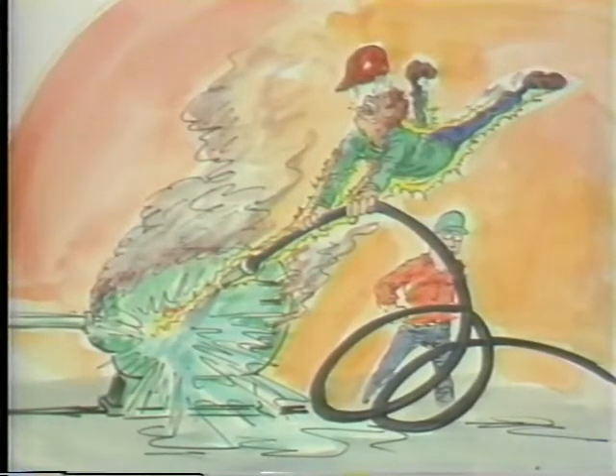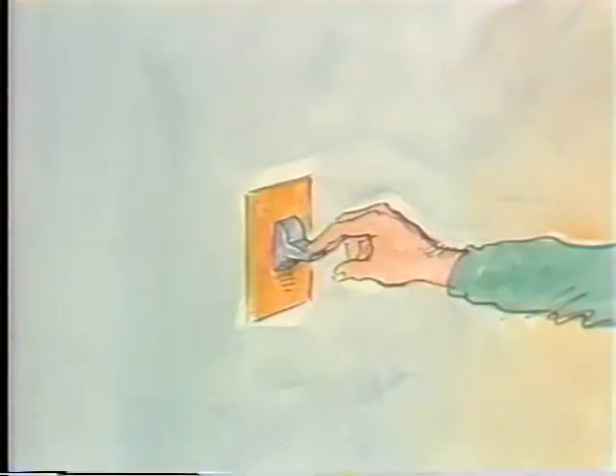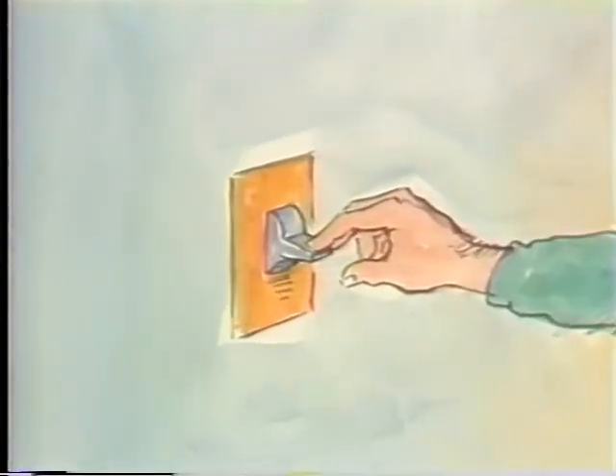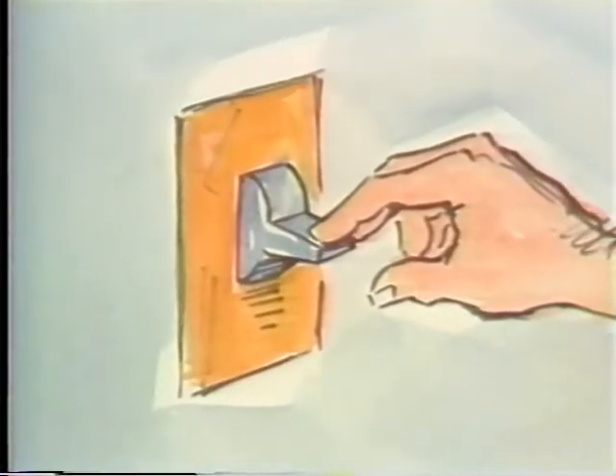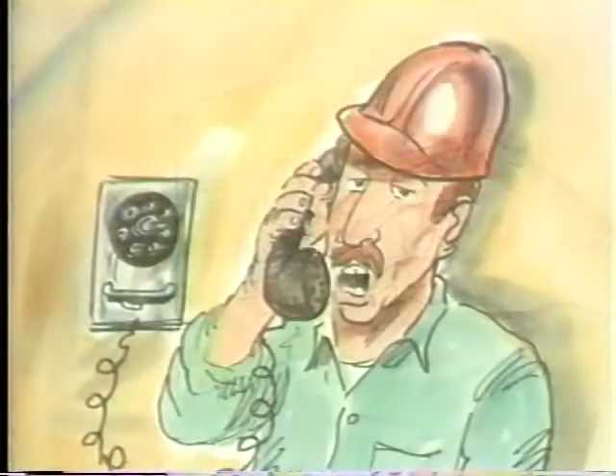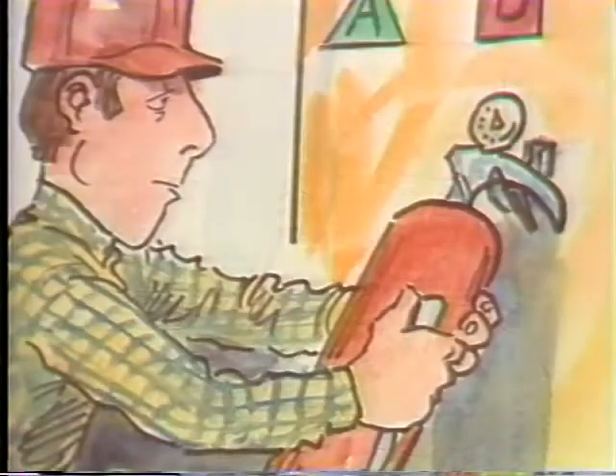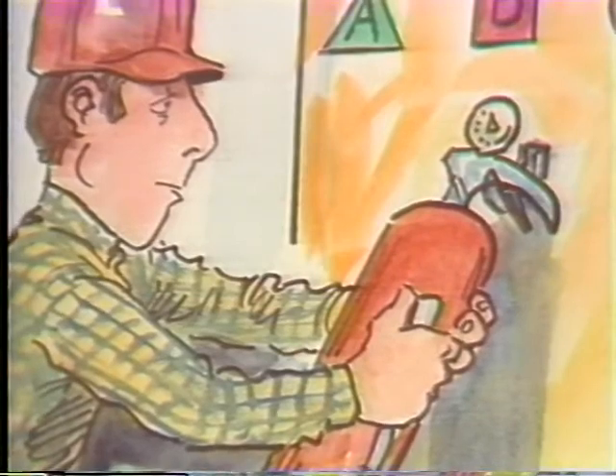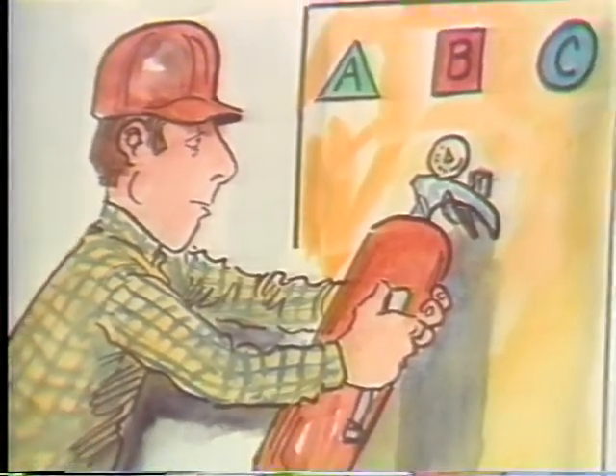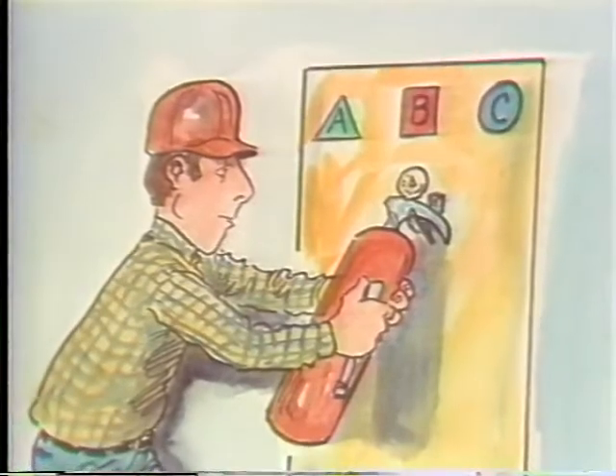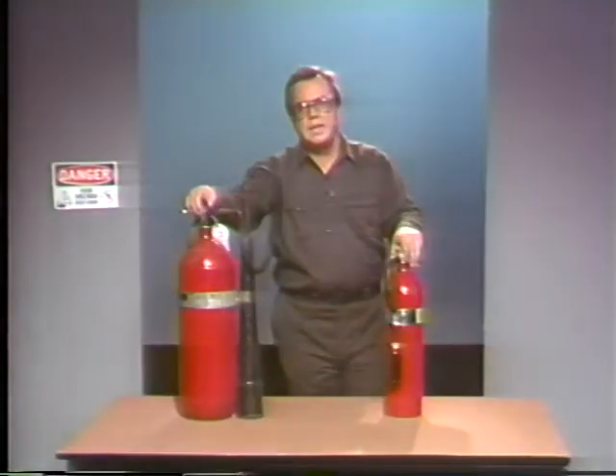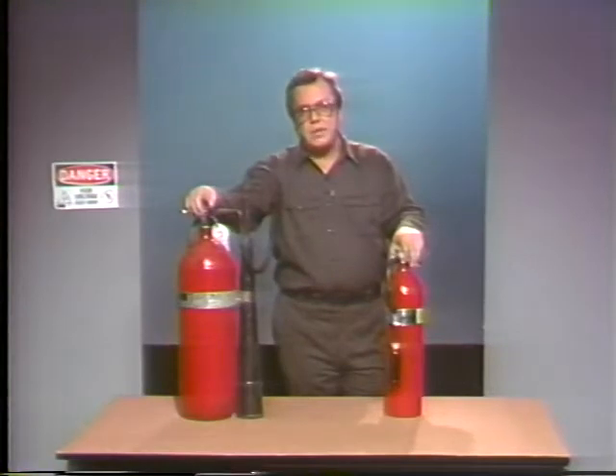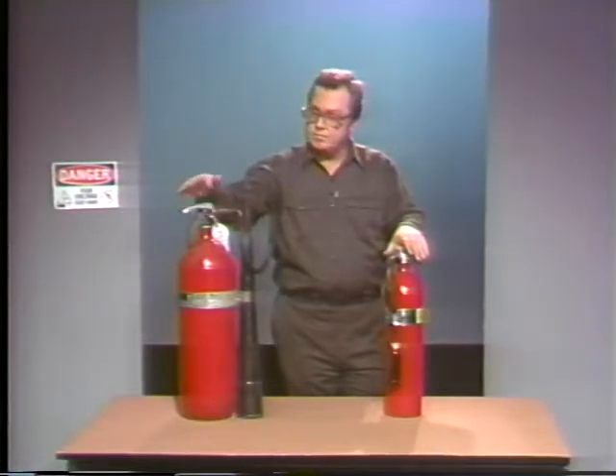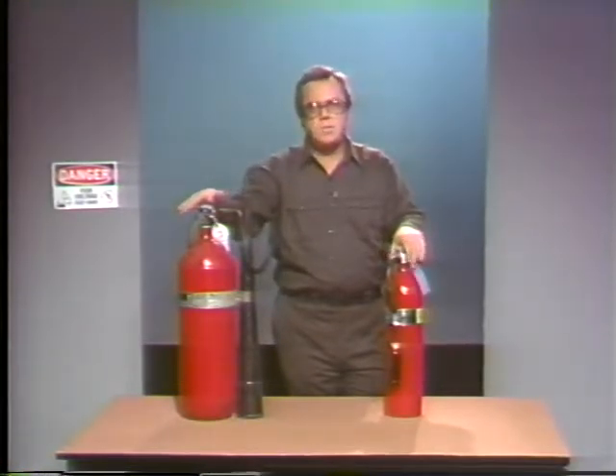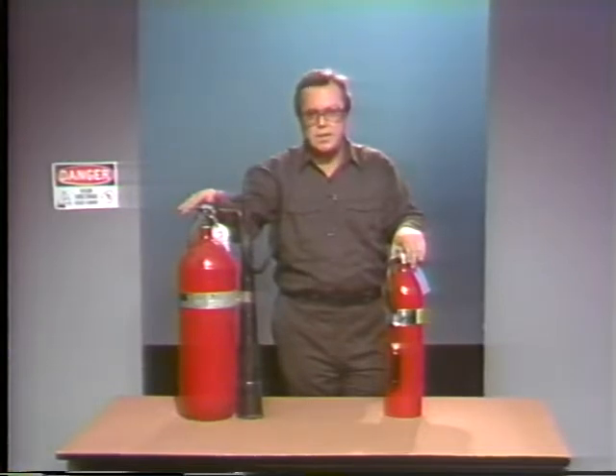Here's what you should do instead for any electrical fire. First, cut the power. De-energizing the equipment removes the ignition source, so the fire will slow down. Second, report the fire. And third, use an extinguisher that's rated Class C for electrical fires. A type rated ABC will handle almost any kind of fire you're likely to run into. In your plant, you'll probably find one or both of these kinds of extinguishers: dry chemical or CO2. They're both effective on electrical fires if they're used correctly.